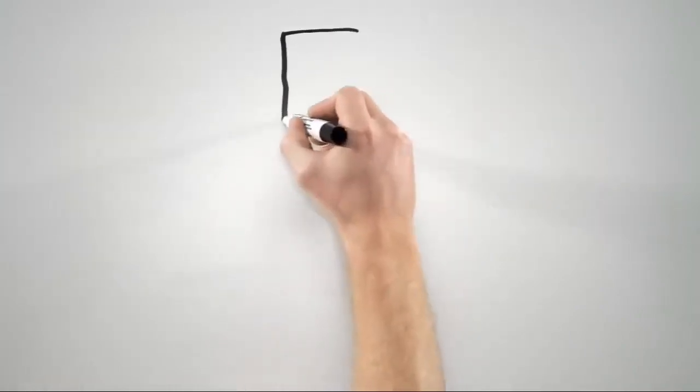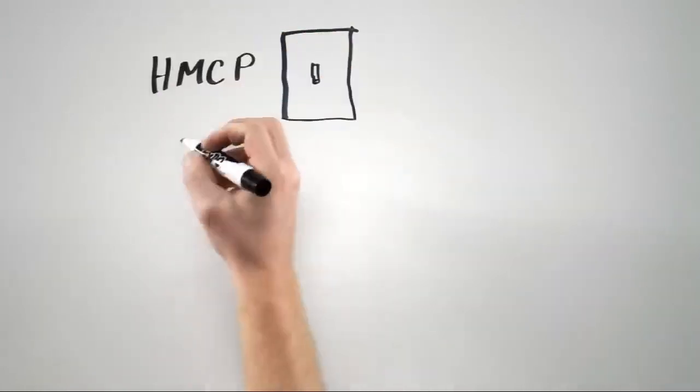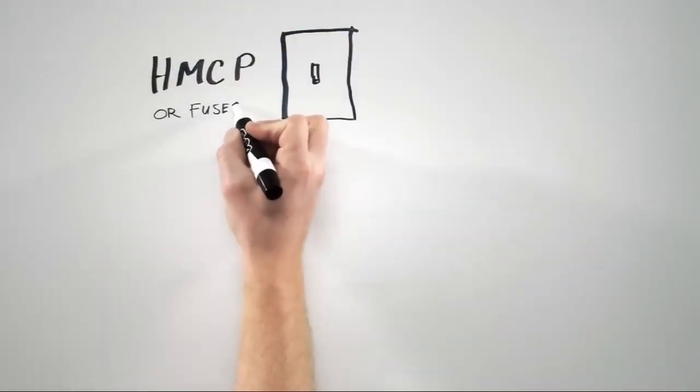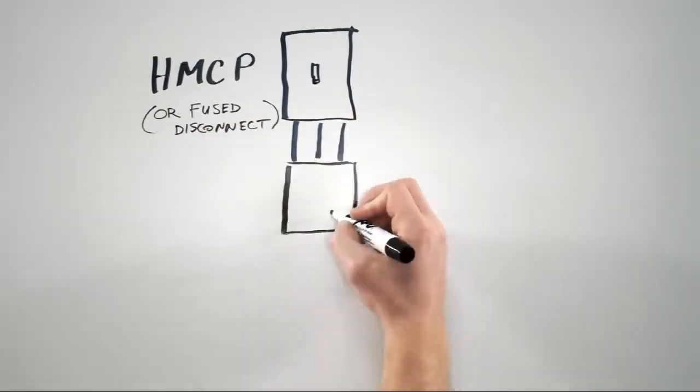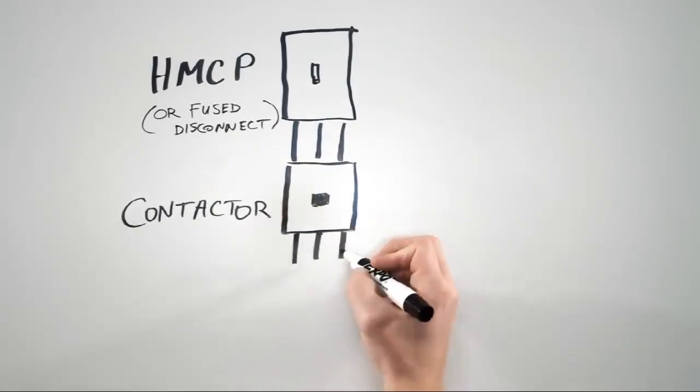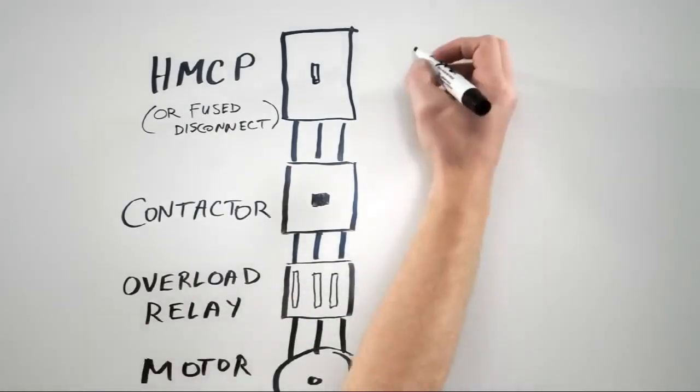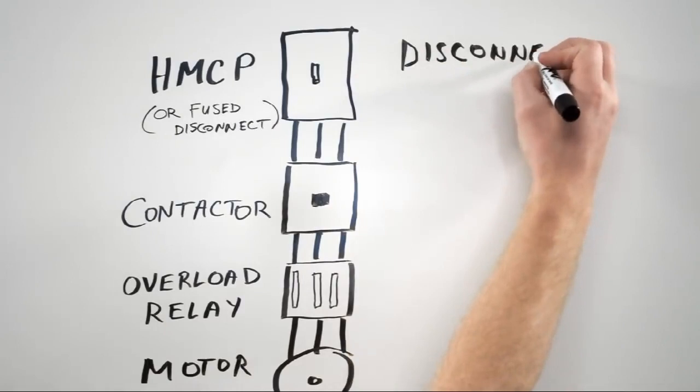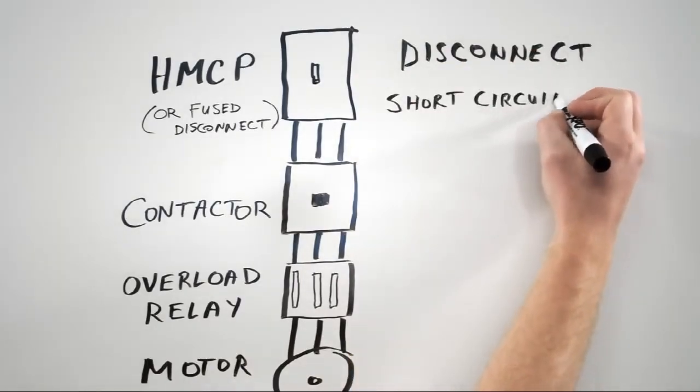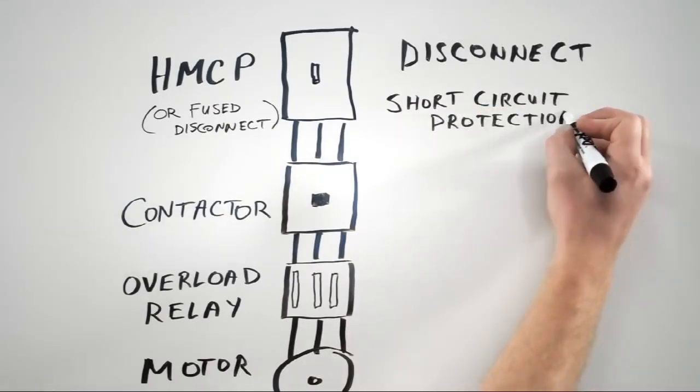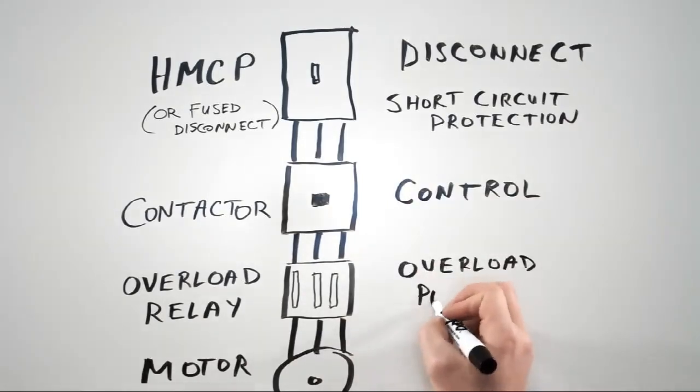Now that we've covered motor protection and motor control, let's put it all together. At the top of the circuit we have our HMCP breaker, or alternately we could use a fuse disconnect switch. Next we have the contactor, followed by the Overload Relay. Lastly, we have the cables connecting the Overload Relay to the motor. In this setup, the HMCP provides a way to disconnect the entire circuit from power, as well as providing short circuit protection, since it still has the magnetic protection inside. The contactor provides a means of controlling the motor, and then finally the Overload Relay protects our motor from overload conditions.